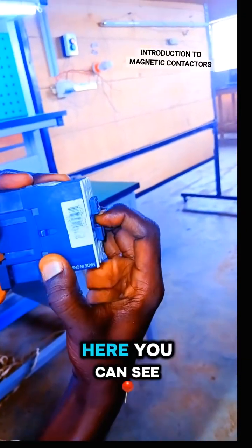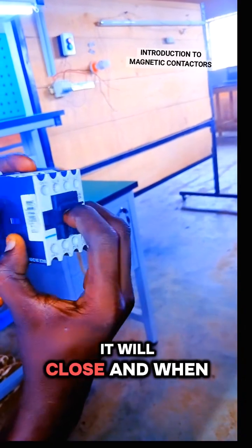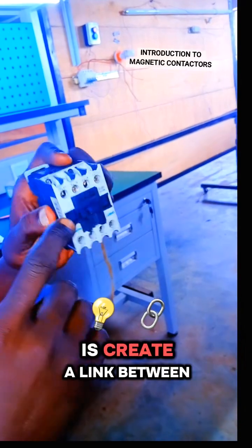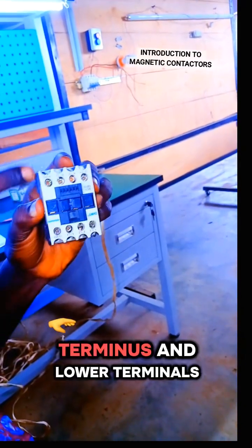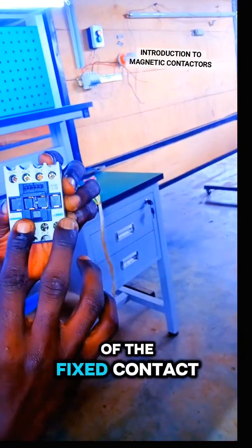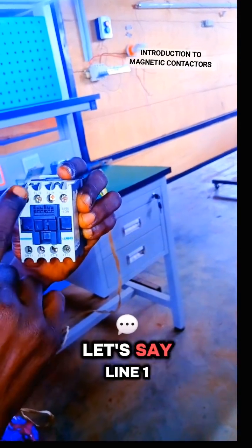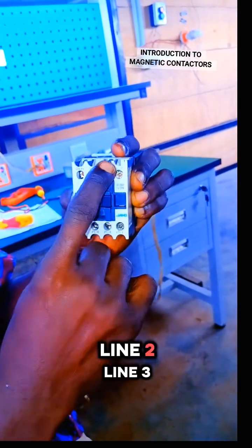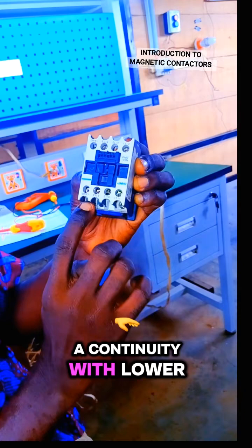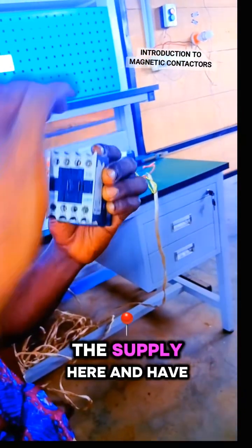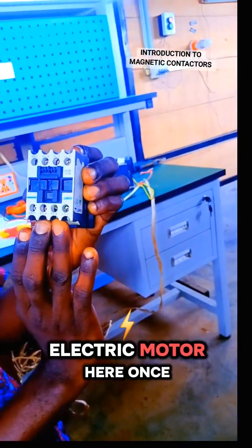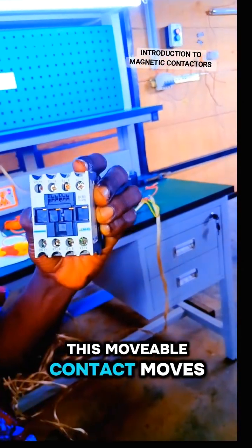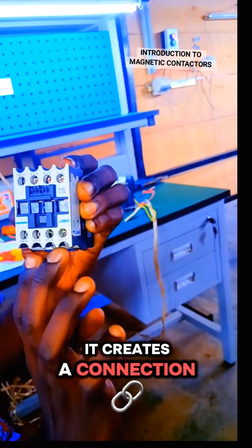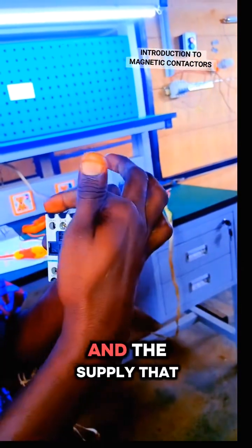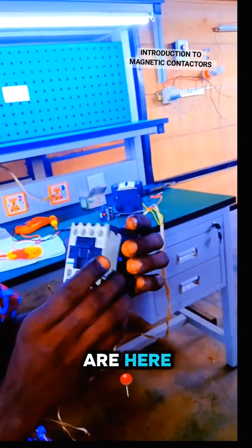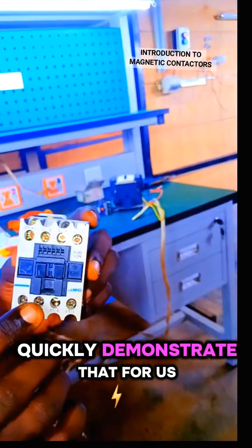If you look at this space here, you can see when it moves like this, it will close. And when it closes, it creates a link between the upper terminals and the lower terminals of the fixed contact. So if I put a supply here, let's say line 1, line 2, line 3, this line 1, line 2, line 3 is going to have continuity with the lower terminals. Assuming I have the supply here and I have an electric motor here, once this movable contact moves, it creates a connection between the terminals of the electric motor and the supply that are here. Let me quickly demonstrate that for us.